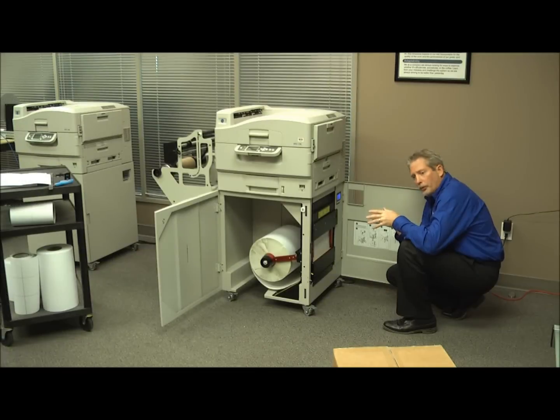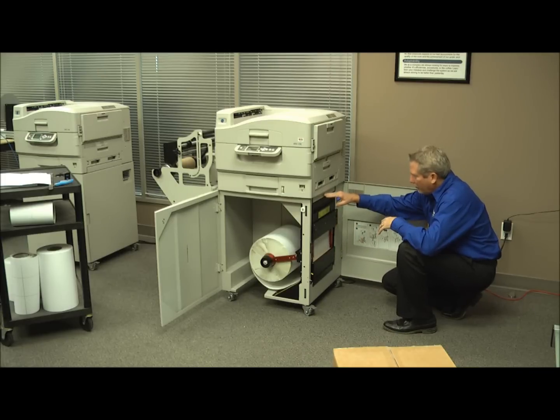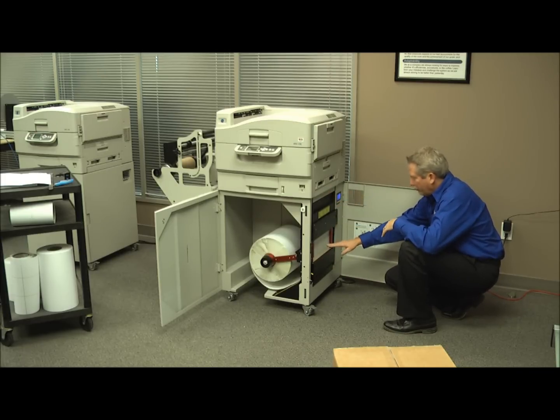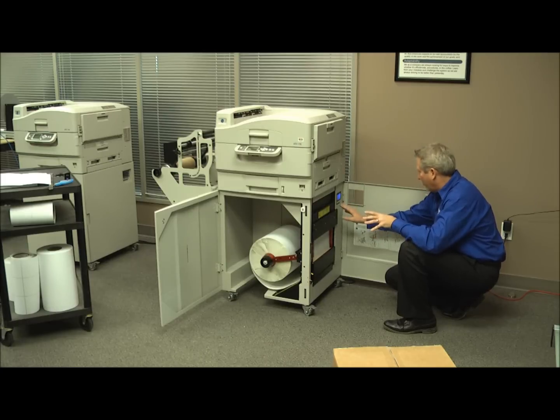So I'm back at my software, and I'm going to run that calibration test again. So we hit run calibration, and my window disappears. Well, that means that the calibration ran perfectly. So we're ready just to reload the media one more time. Takes 2 seconds, and then we're going to start doing the label setup. So through sensor calibration, we actually have to remove the media, the actual start position, which is actually up here, to do the proper calibration for the sensor. So all I got to do now is just go through the reload.